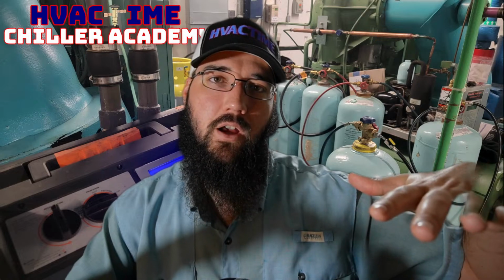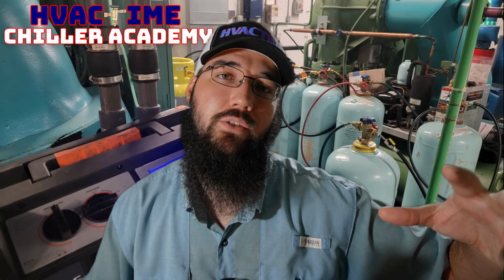So with less load on the compressor, higher discharge superheat. As the compressor loads up, and all else being proper, your flows are good, your refrigerant charge is good, your set points are good, you will actually see your discharge superheat lower as the compressor loads up, because we're feeding more total volume into the compressor. That is a very clear distinction between what you might experience with a variable speed and what you'll see with a constant speed. So with a constant speed, seeing a high discharge superheat at low load conditions is actually normal. But you should see that discharge superheat begin to come down as the load increases.